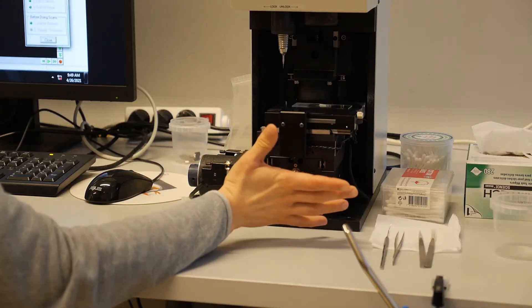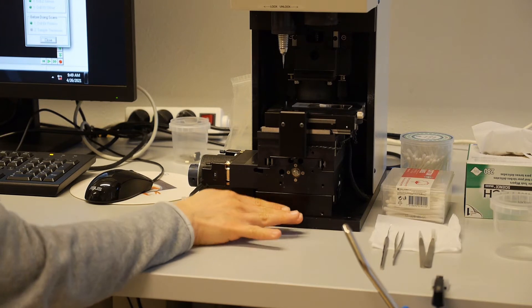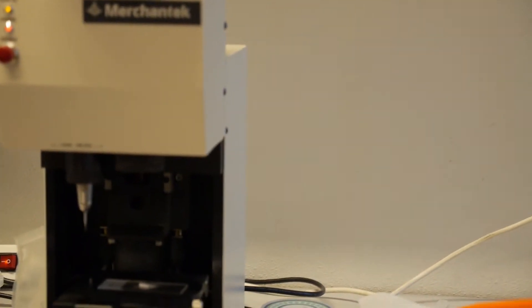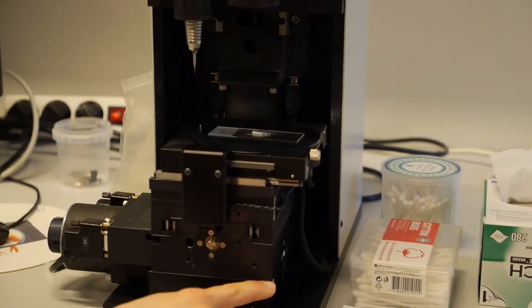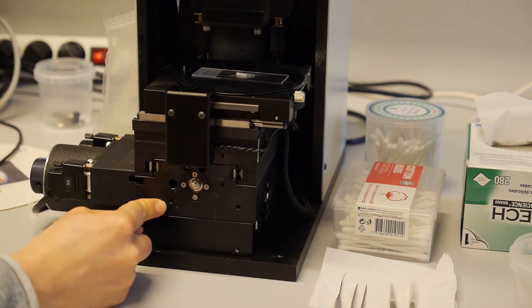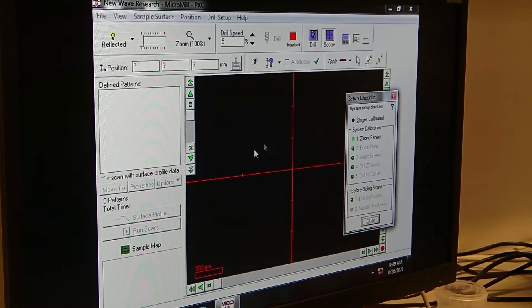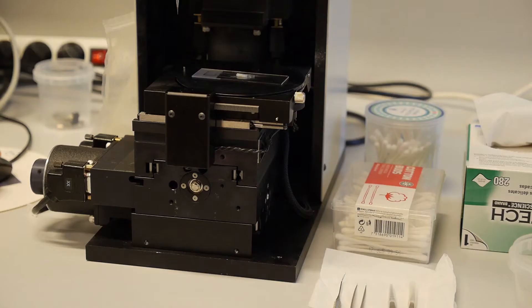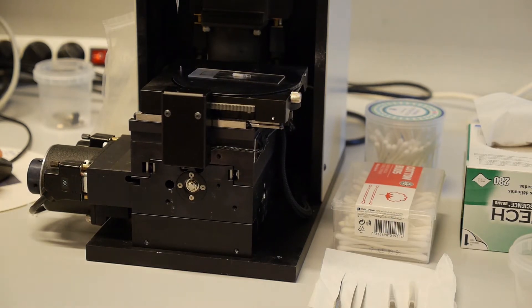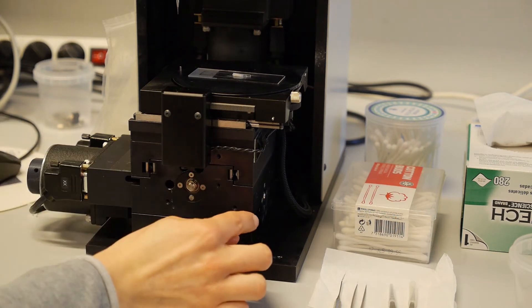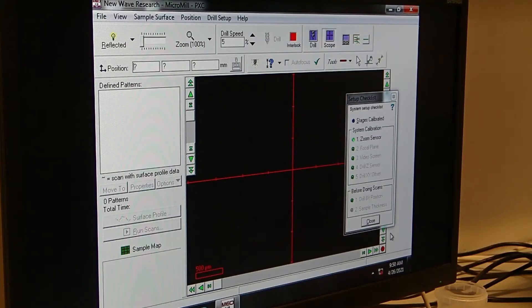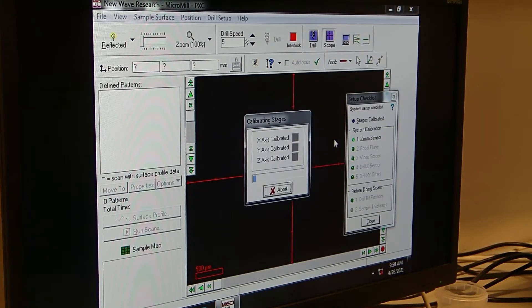For the stage calibration, you do have to have a look at the micro mill itself. You can see these three different black boxes or blocks and they do have to be aligned. You can see that here, for example, it is not properly aligned. So I can move the stages manually by using these green double arrows on the screen. So as you can see, if you press to the right side, it's moving to the left, so don't be confused by that. And then I just feel if they are aligned. So it doesn't have to be one micrometer correct, it's just that it feels like they are aligned. Once you feel comfortable about it, you do click on stages calibrated.